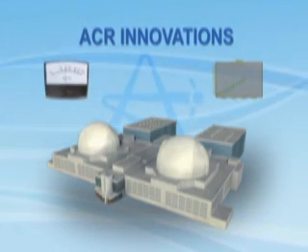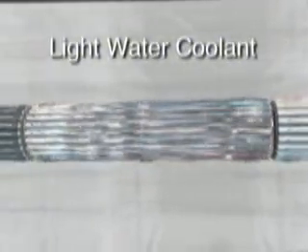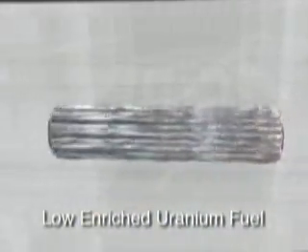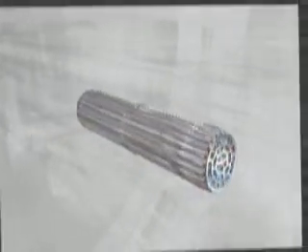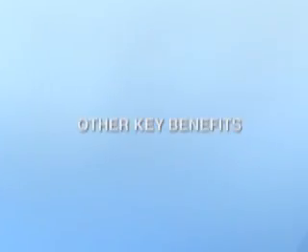Design innovations have been made to the ACR to enhance its economics, output and safety. The reactor's heavy water inventory has been reduced through the use of light water as the reactor coolant. Low enriched uranium is used in the fuel bundles, which results in a smaller volume of spent fuel per megawatt hour. Improved performance has been achieved through the use of smart CANDU diagnostic systems.